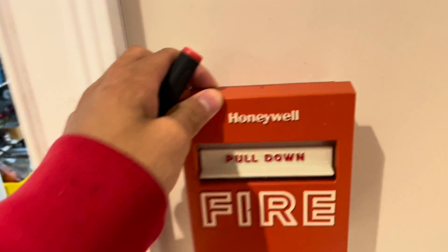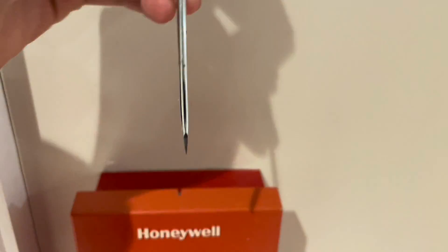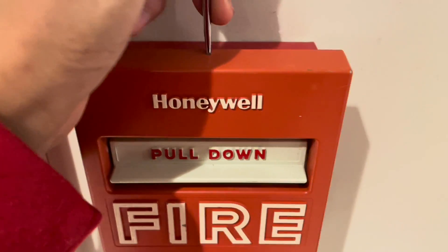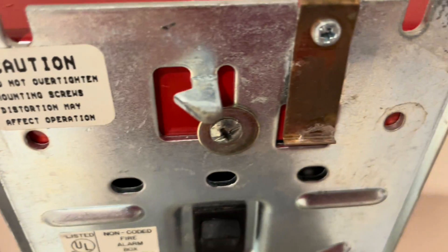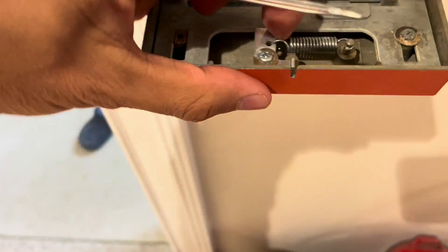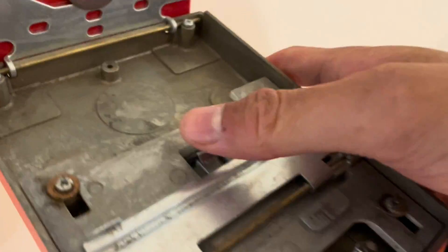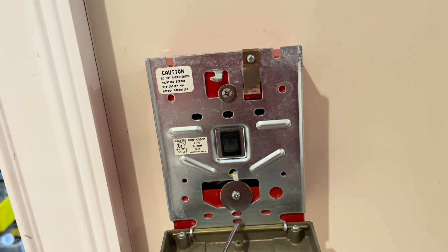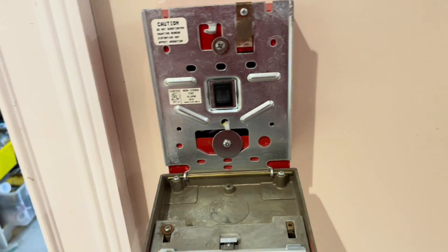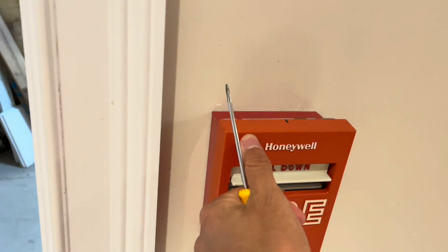To reset this pull station you don't necessarily need a special tool. You're supposed to use a thin flat head screwdriver — you just stick it in and it opens. There's a spring-loaded tab that latches into place, and by pulling it you release and flip the switch. The newer versions have a little plastic switch which I kind of like, and it flips down when you pull it. I had to rig it up to the back box using washers because the actual mounting holes would have sunk the unit down — but it looks legit, which is good.